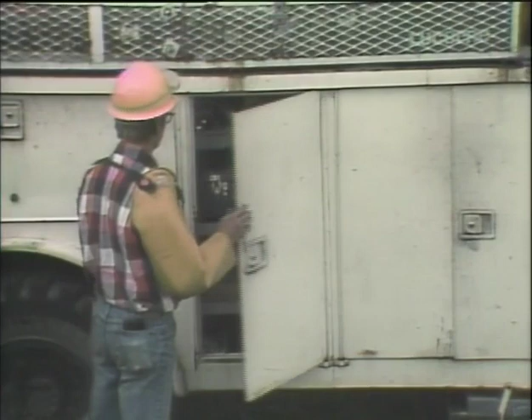The crew leader radios the dispatcher to get the go-ahead to proceed with the job. "I'd like to install my tag and grounds on 69069, pole last 4, 9994." The dispatcher gives the crew clearance to test for dead and install protective grounds. Although the dispatcher relays the status of the circuit, the line crew still assumes the circuit is energized until the lines are tested. The worker who will be testing and grounding wears protective equipment.